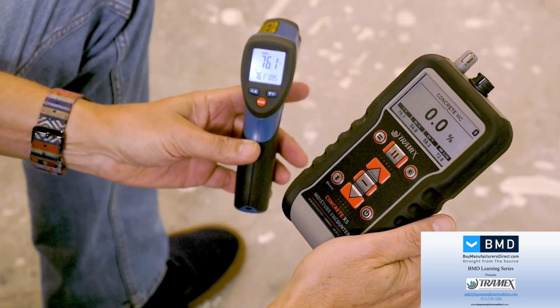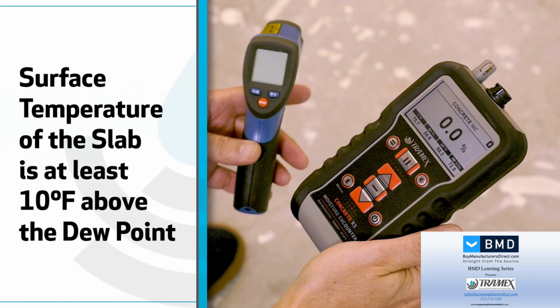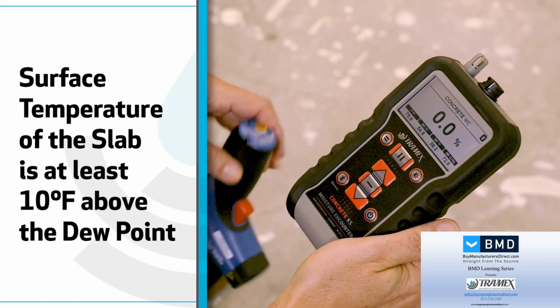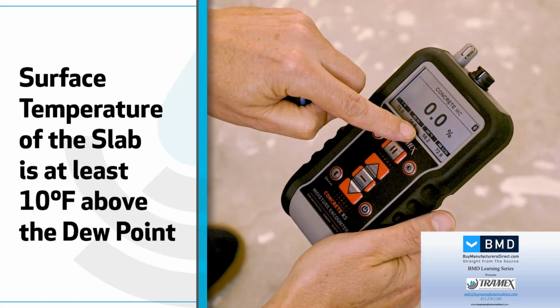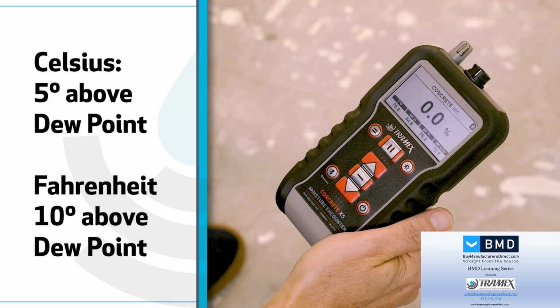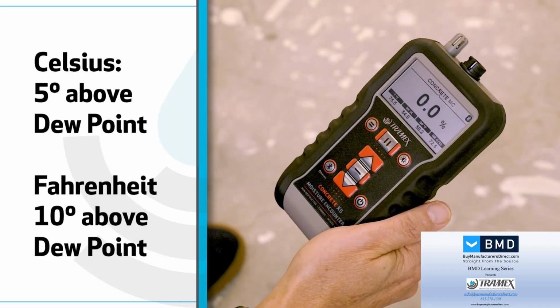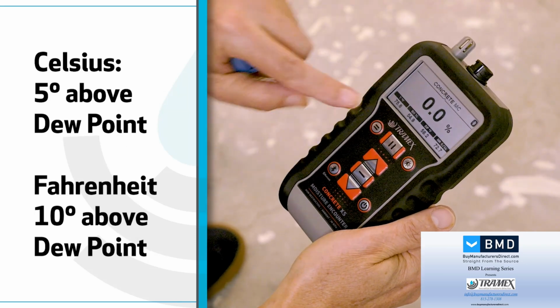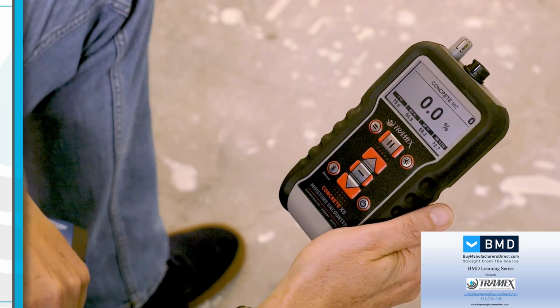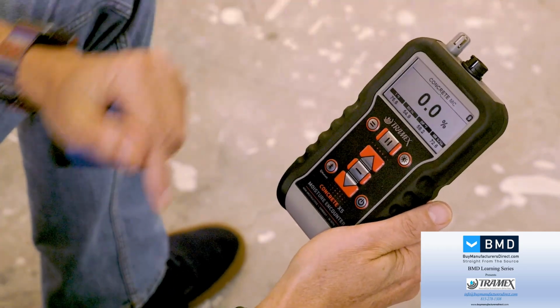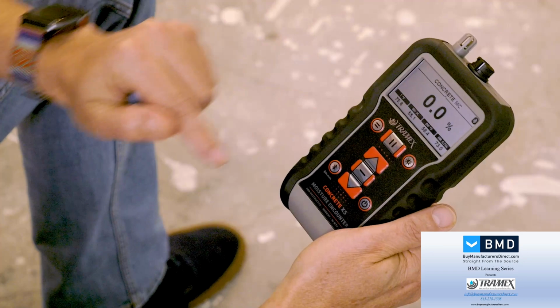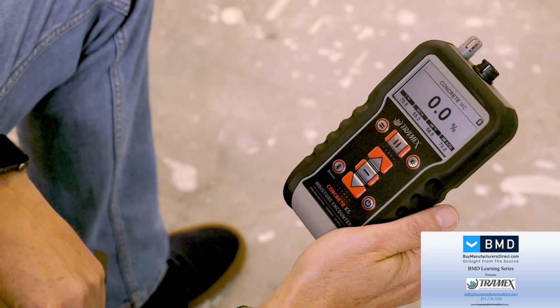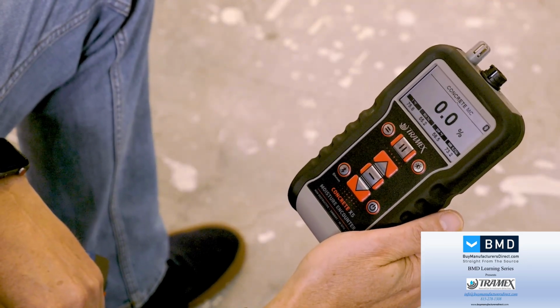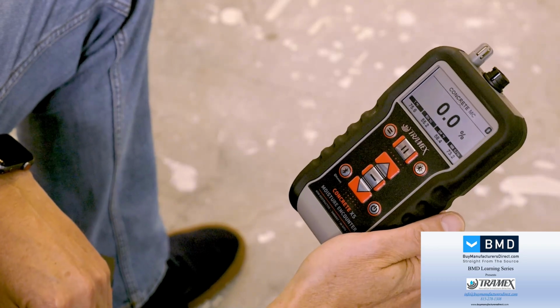So we just want to make sure that the surface temperature of the slab is at least 10 degrees Fahrenheit above the dew point. If you happen to be working in Celsius, you're going to keep that number at 5. But here we have the meter set at Fahrenheit. There is an internal setting where you can switch to Celsius. We're working with a Fahrenheit number, and we've made sure that we're at least 10 degrees above the ambient dew point with the surface temperature of the slab.